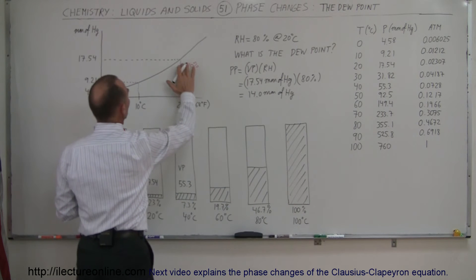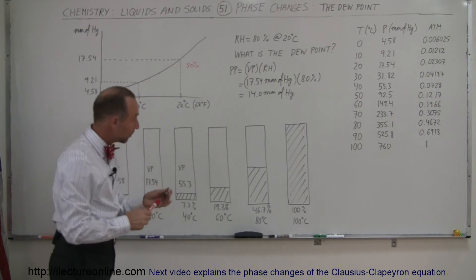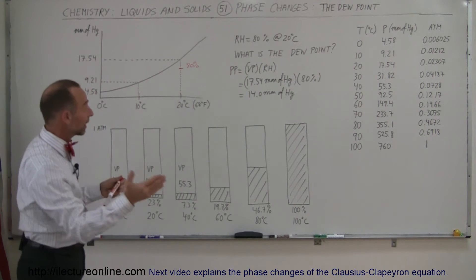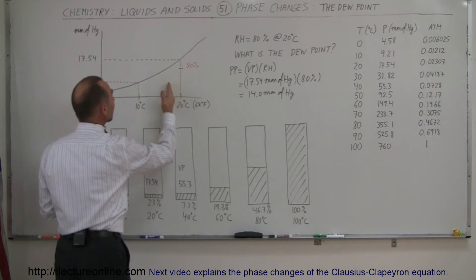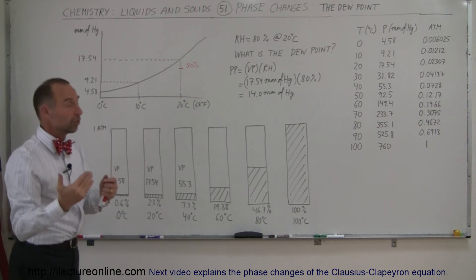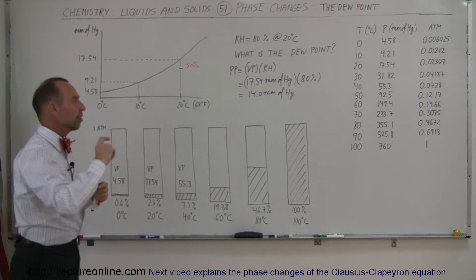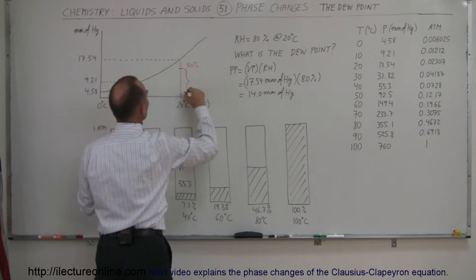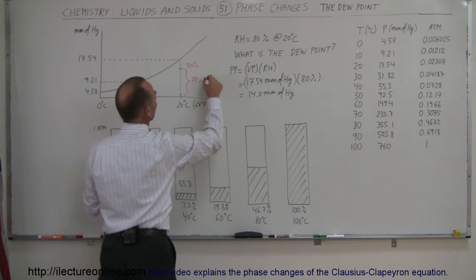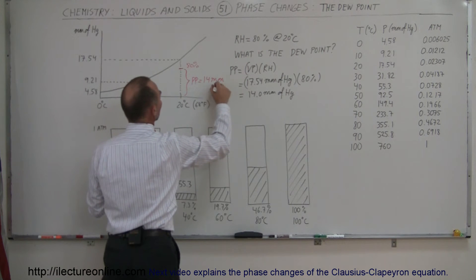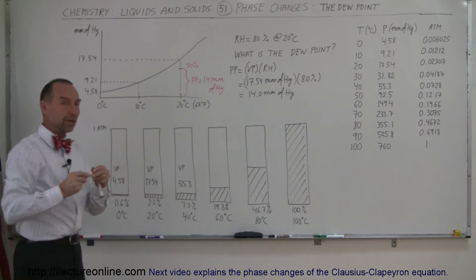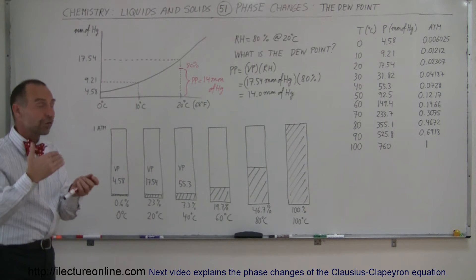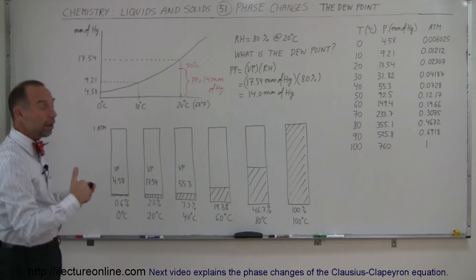So 80% is marked on the graph. Now the temperature begins to decrease: it becomes 19 degrees, 18 degrees, 17 degrees. The amount of moisture doesn't change, but as a percentage — the partial pressure, which is equal to 14 millimeters of mercury — that doesn't change. However, how much moisture the air can hold depends on the temperature. As the temperature decreases, the air can hold less and less, and the partial pressure becomes a larger fraction of the vapor pressure.